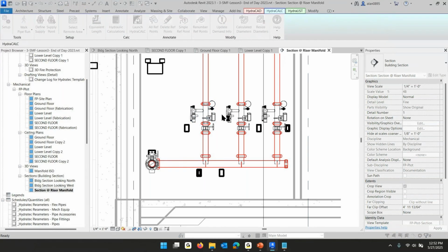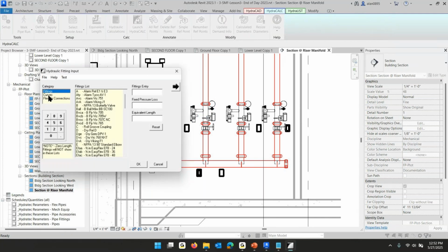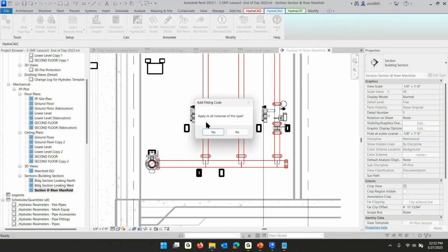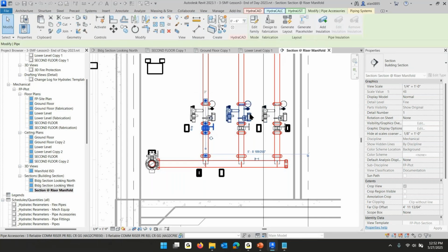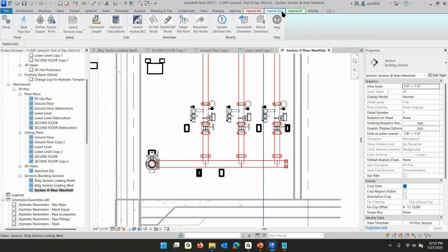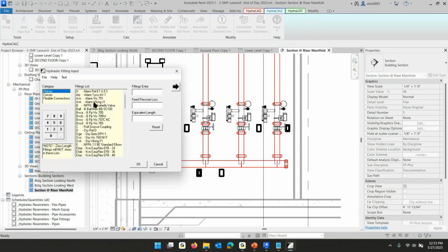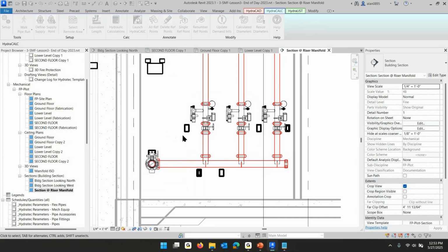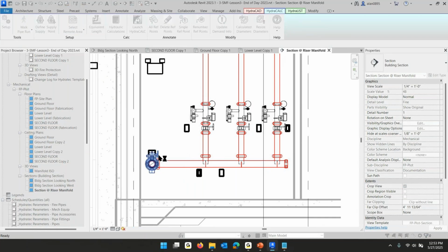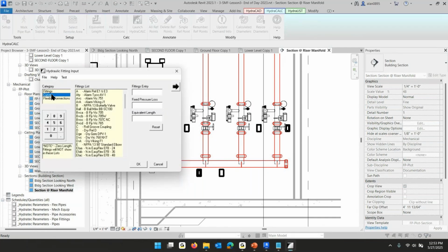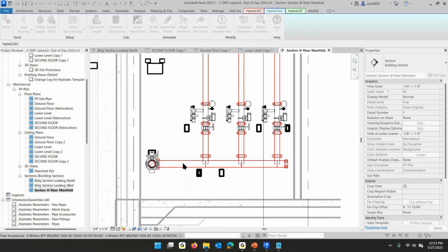Click on this thing. And James, this looks familiar to you. I'm going to use the flow switch curve and apply that to all of those. So a flow switch will get calculated on all of those. And then I'm going to go to equivalent length, pick on the butterfly valve, and just pick butterfly and OK. Apply that to all of them. And I'm going to do one more time on the backflow device. That's a curve that comes from this Wilkins 350A. And apply that.